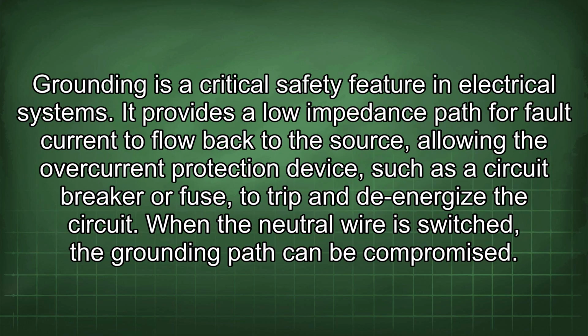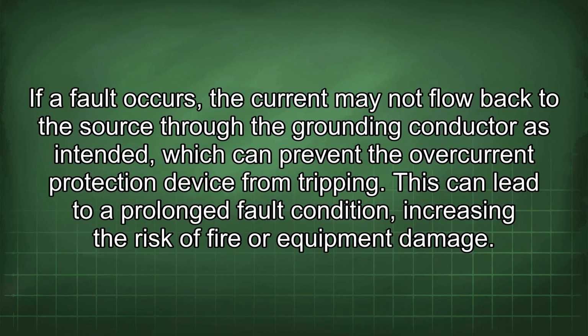Grounding is a critical safety feature in electrical systems. It provides a low impedance path for fault current to flow back to the source, allowing the overcurrent protection device, such as the circuit breaker or fuse, to trip and de-energize the circuit. When the neutral wire is switched, the grounding path can be compromised. If a fault occurs, the current may not flow back to the source through the grounding conductor as intended, which can prevent the overcurrent protection device from tripping. This can lead to a prolonged fault condition, increasing the risk of fire or equipment damage.